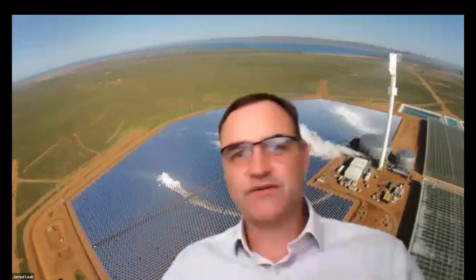There are a couple more questions. Go Brendan. Sorry, yeah. I was just going to say about the thermal storage. I think there's a few questions about what temperature. Did anyone consider geothermal? There's a few questions just around thermal storage that can probably be answered collectively. The temperature is around 50 degrees that the thermal storage is held at. The answer to geothermal, I don't know actually if it was considered because they're air source heat. We have air source heat pumps, which do have some issues occasionally with some of the colder temperatures that we get.